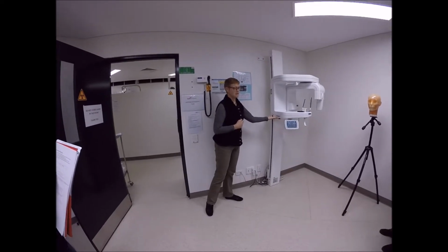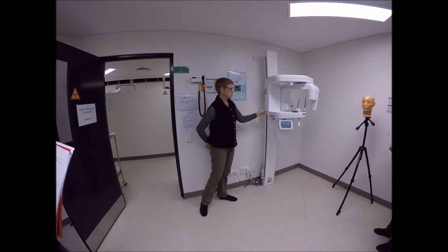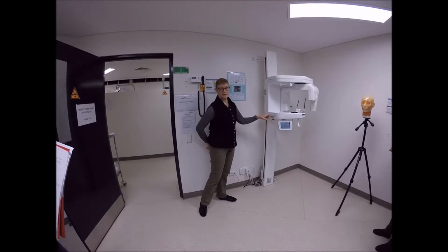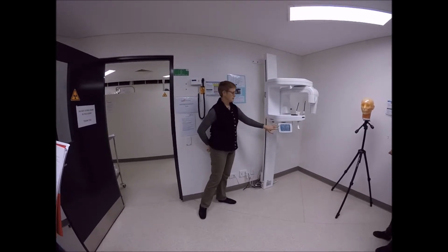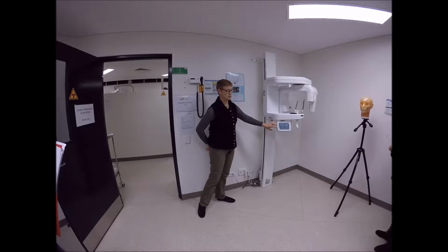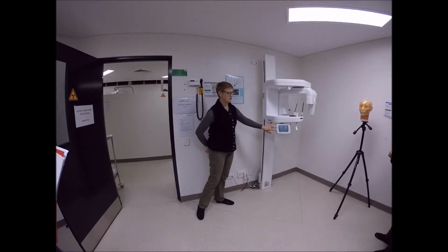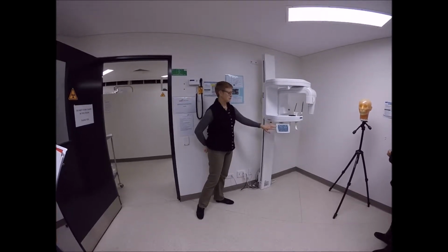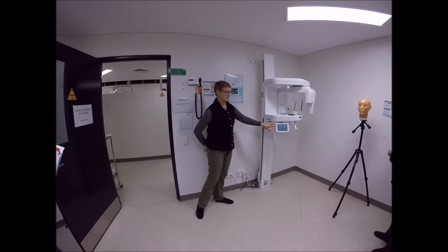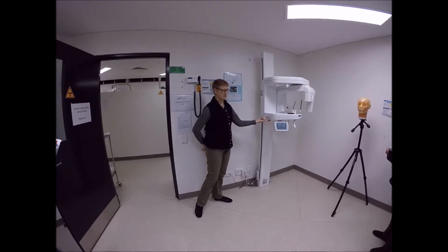When you switch that on, the software of the machine will run through a series of checks. If the machine's in good order, it'll show a normal display on the touch panel. If there's a problem, it'll give an error and you'll need to call a technician because you won't be able to use the unit. This machine has an emergency stop button, which is the red button under here.